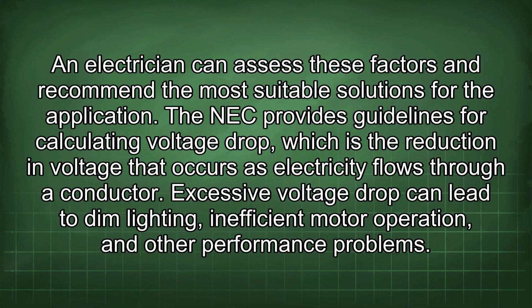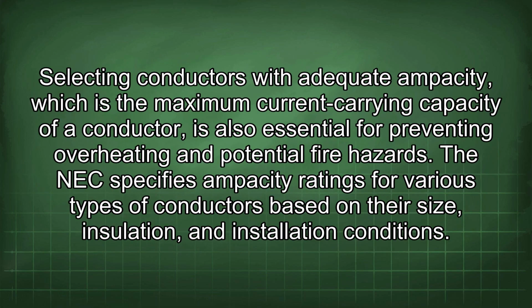The NEC provides guidelines for calculating voltage drop, which is the reduction in voltage that occurs as electricity flows through a conductor. Excessive voltage drop can lead to dim lighting, inefficient motor operation, and other performance problems. Selecting conductors with adequate ampacity, which is the maximum current carrying capacity of a conductor, is also essential for preventing overheating and potential fire hazards. The NEC specifies ampacity ratings for various types of conductors based on their size, insulation, and installation conditions.